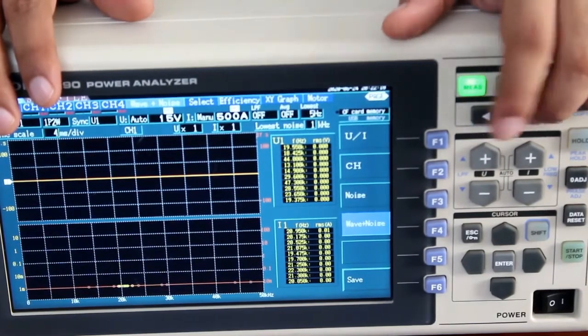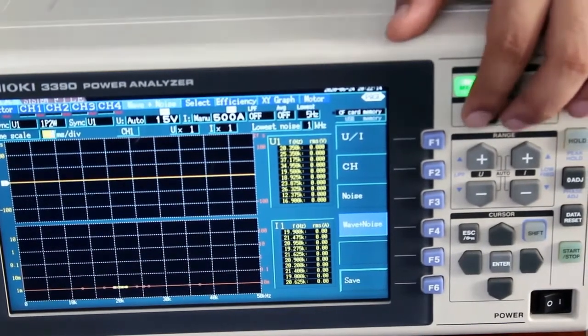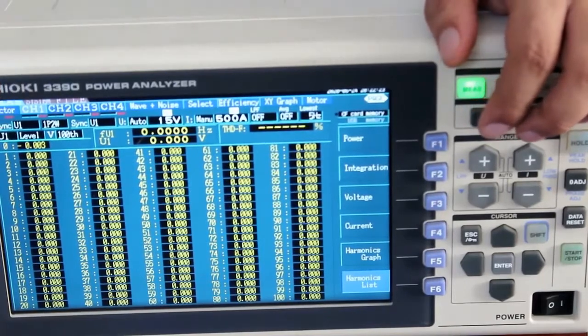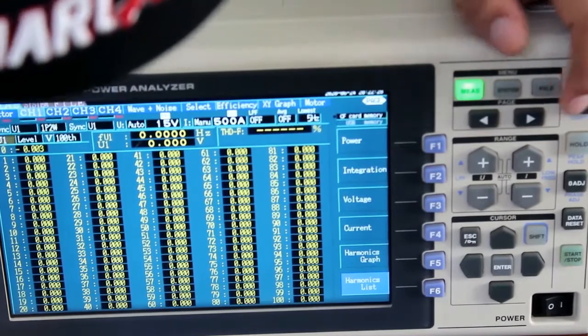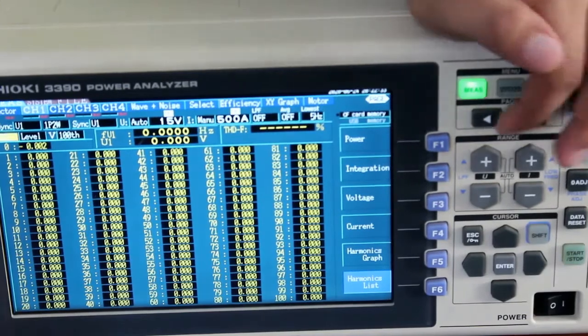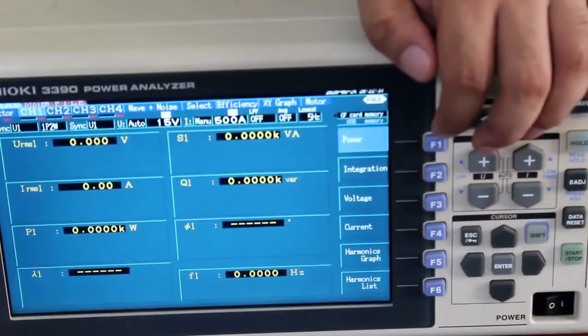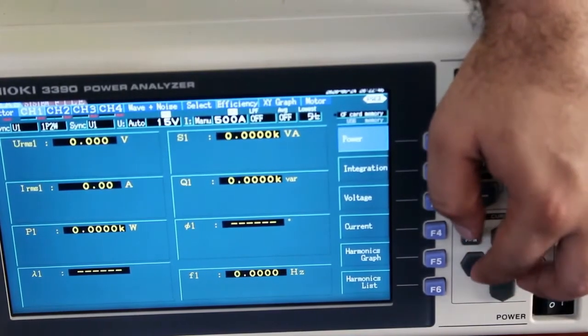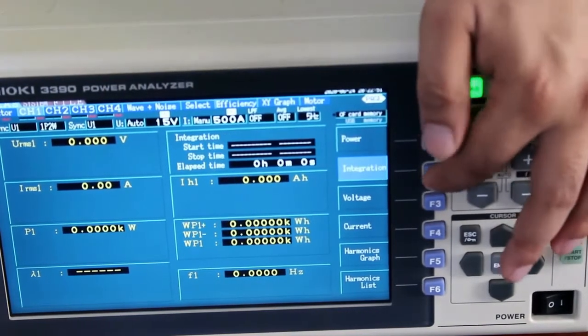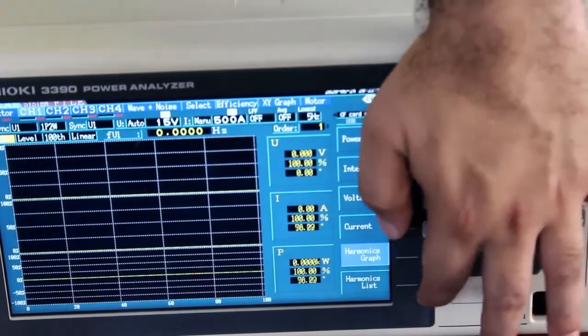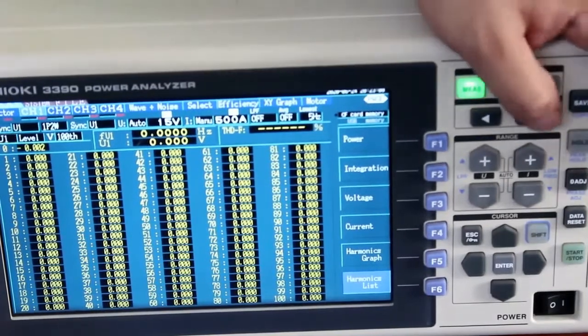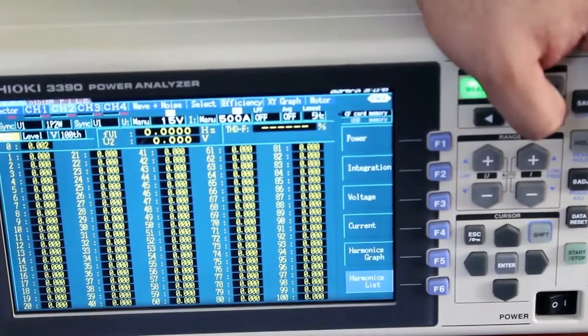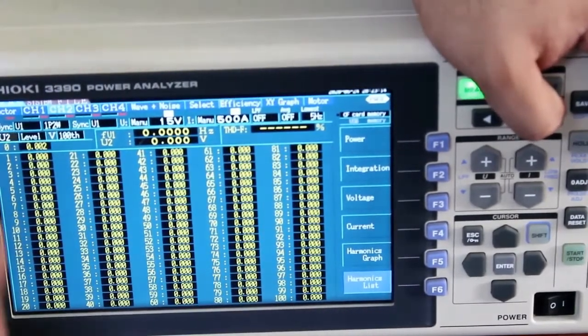Press the key and then the page toggle key to get to the measurement screen. The first screen shows channel one parameters, including phase-wise parameters. Pressing F1 brings up power parameters, and navigation keys let you select specific items. Integration, voltage, current, harmonic graph, and harmonic list can be seen here. Pressing the page key toggles to the next phase and so on. Basic parameters like frequency and selected ranges are also shown.